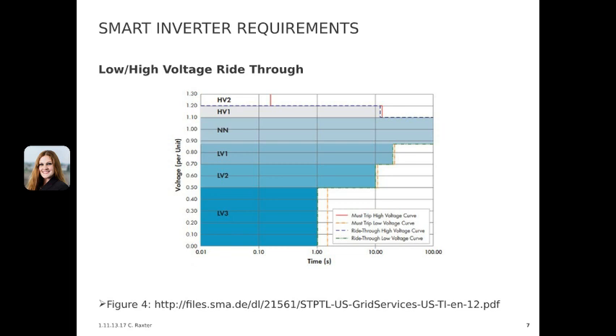With this, the utility can predetermine the voltage percent, whether it's on the high or low side, and the time as to how long they figure these instantaneous dips or bumps could potentially last, and program the DERs to react in that manner. So they will stay connected, although not providing power, and wait that predetermined amount of time to see if the grid voltage stabilizes, and if it does, it remains connected and continues to produce power at that point in time. This is to help prevent a cascading failure. The general disconnect time would be about 5 minutes, and being able to ride through low voltage bumps reduces potentially losing a significant amount of electricity generation for a longer period of time.